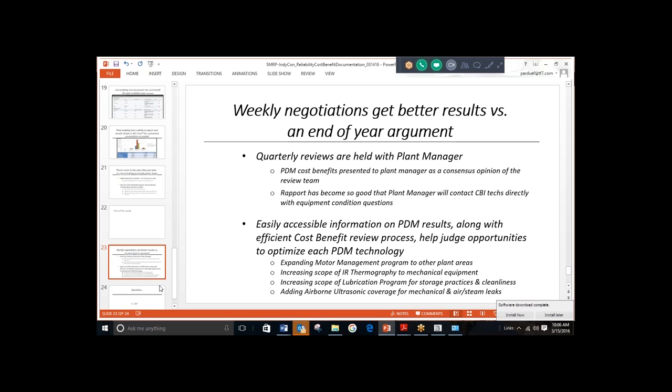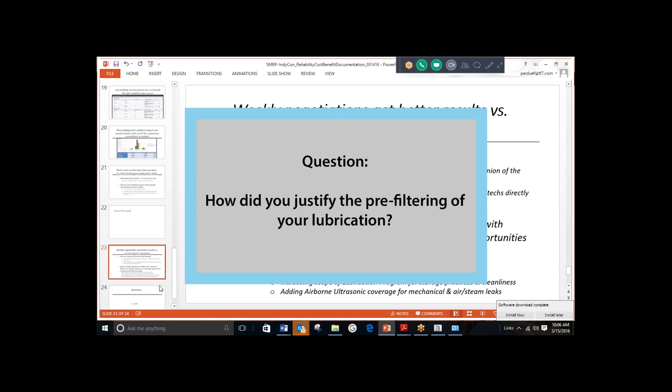Look, Ed, I send in all the Tango reports, the condition entry reports, and he looks at that too. It's pretty interesting how much AC and myself are finding. The new guys, you know, they report problems too. I like this approach this weekly find of the week. Sometimes, I mean, one of the things we're doing now is when Charlie reports a problem, say it's a high vibration due to alignment or whatever, and then we schedule a couple of craftsmen to go out and realign that pump, then he'll send me the results, and you'll see the levels of the vibration drop down a lot. Well, our plant manager has now become really interested because he can relate to a line that peaks and then drops way down back in below the normal range. So he's gotten to where he kind of expects to see those kinds of results, and if we could formalize that a little bit more, that would be even better.